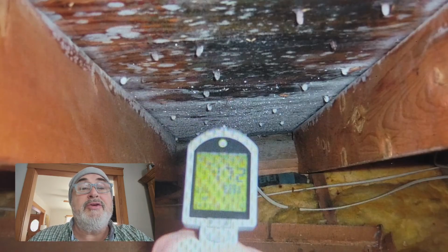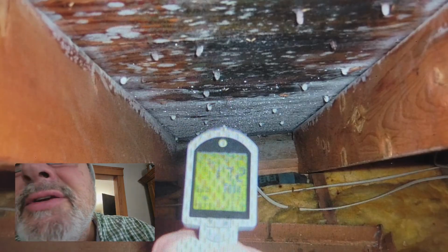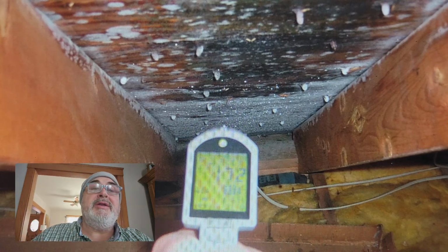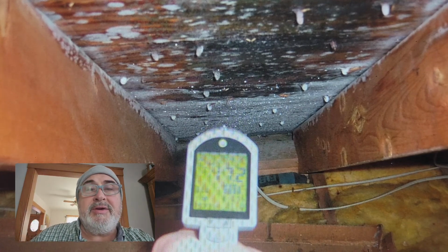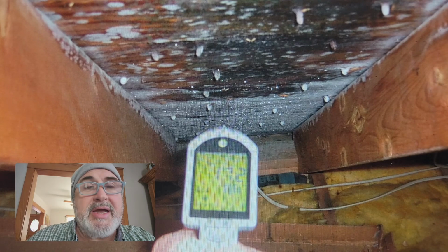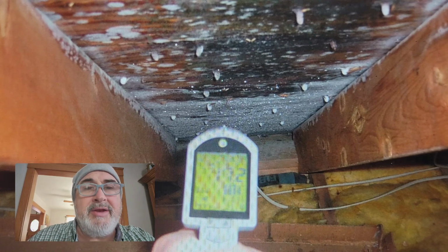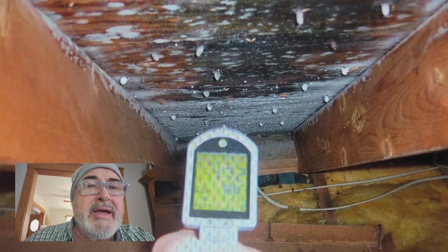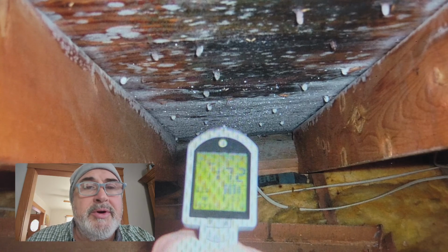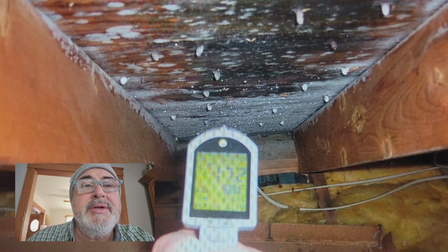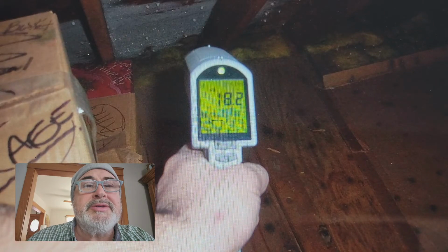All right, and you can see the dew points getting formed. 17 degrees is that surface temperature, and you don't need to be an engineer. You don't need to know your psychrometric charts like I do, all that kind of calculations. But you don't need it. Just look. Black, dark staining. That means in the winter, humidity, condensation, poor HVAC balance, thermal bypass.